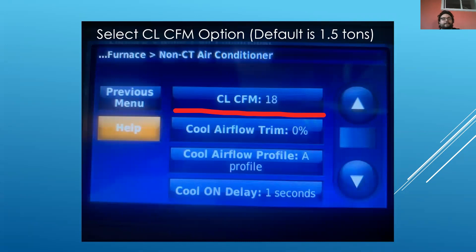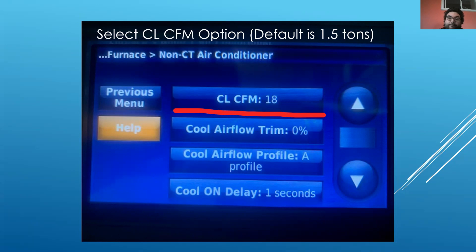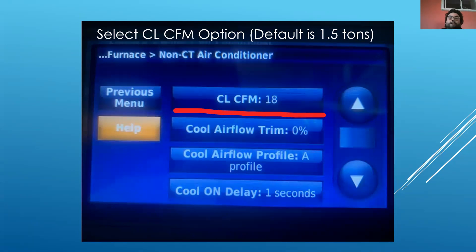The first thing you're going to see is CL CFM and then 18. It comes default from the factory showing 18, which means 18,000 BTUs or one and a half tons of cooling. So if you don't change this — say you install a three-ton air conditioner — it's only going to give you a ton and a half of airflow, which will freeze up a coil pretty quick. It's important to go to the setting and make sure it's correct.